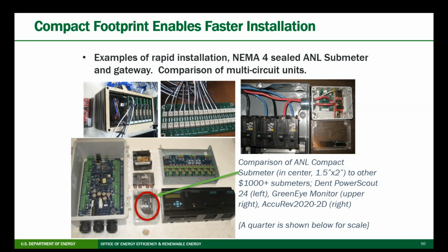In the upper right, I wanted to focus on cost. In the middle there's a 1-inch nipple with a lock ring, which I found is the fastest way to mount a meter. On the right is a $5 NEMA 4 enclosure, and the red board is that sub-$20 gateway, with the meter in the center with the power leads. In this case, the power goes directly in and out; other installs would just be the signals from the current sensors. With this nipple, I've installed these in under 10 minutes start to finish, including taking the panel cover off and commissioning it. So that's what I've been focusing on: time, materials, and labor.